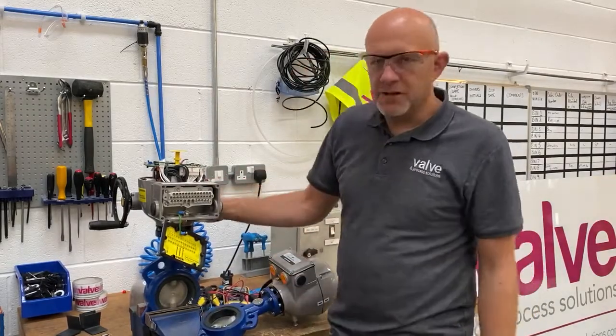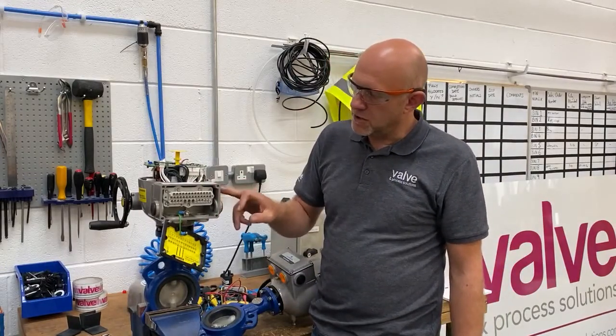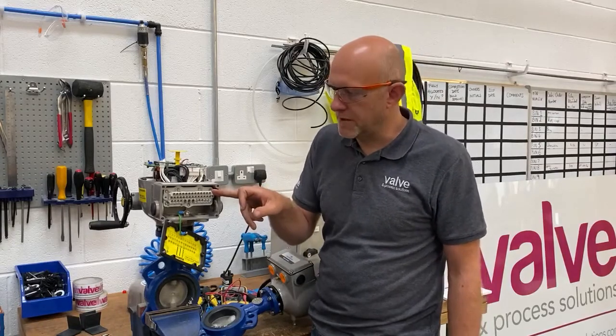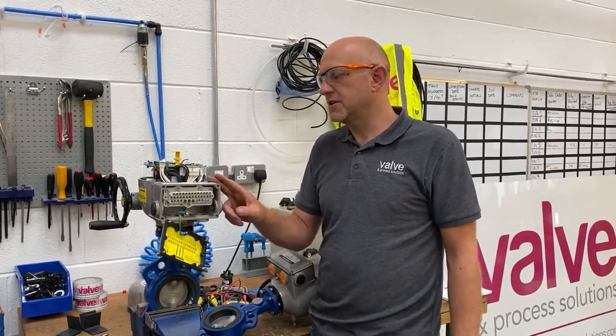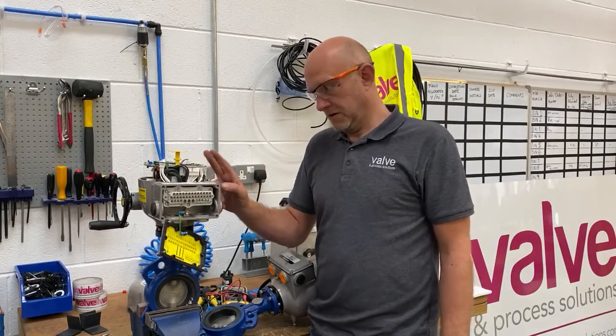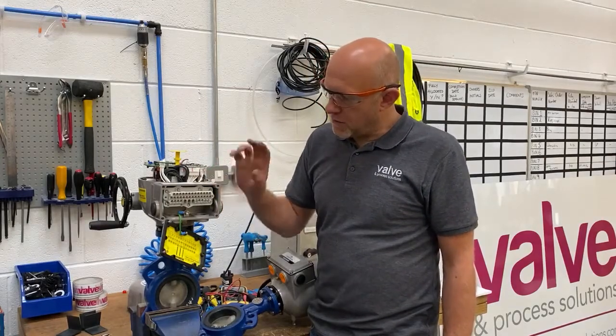What we're doing is we're fully stroking the valve open and closed and setting the limits. And also we're checking to make sure that the actuator gives the signal for the open and closed limits. And in the same process, we're also changing the actuator to its fastest speed setting because the customer would like it set that way.